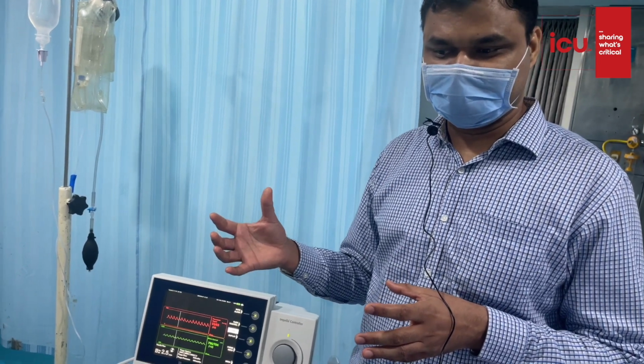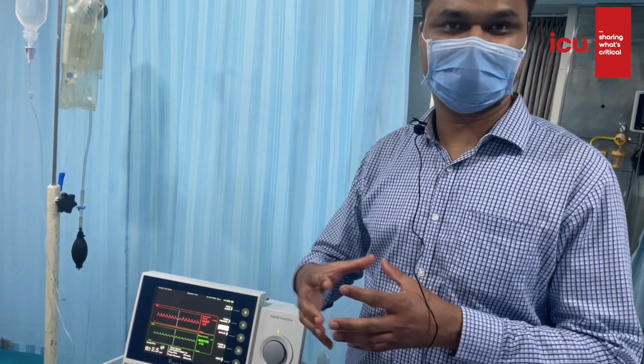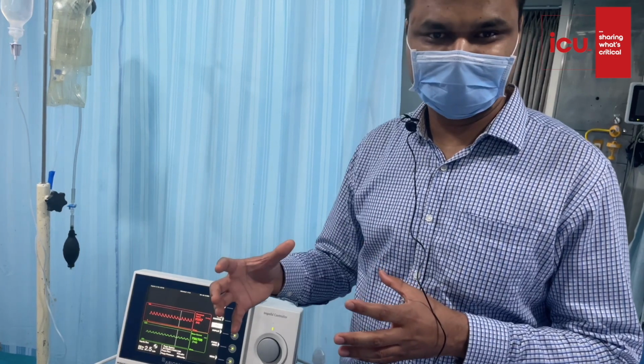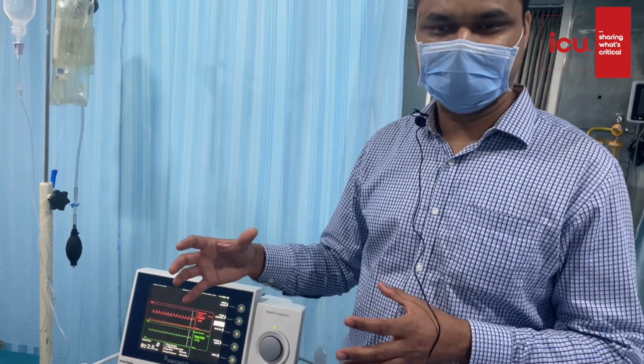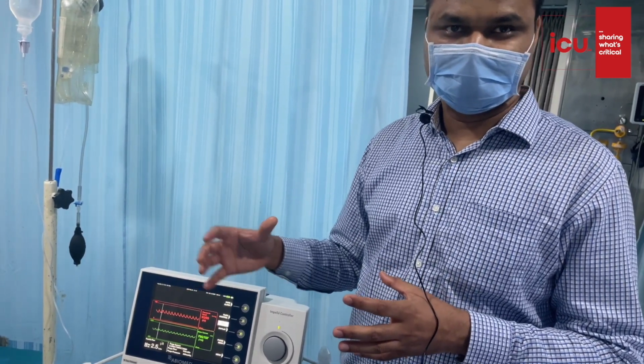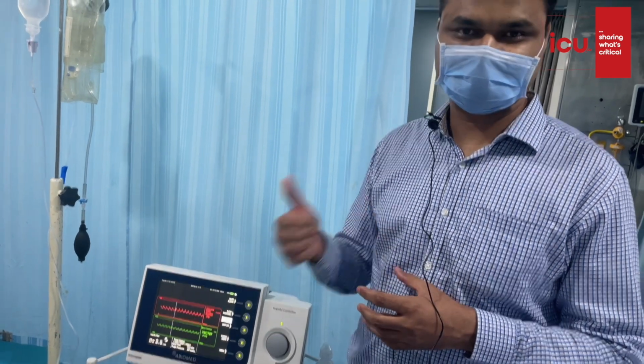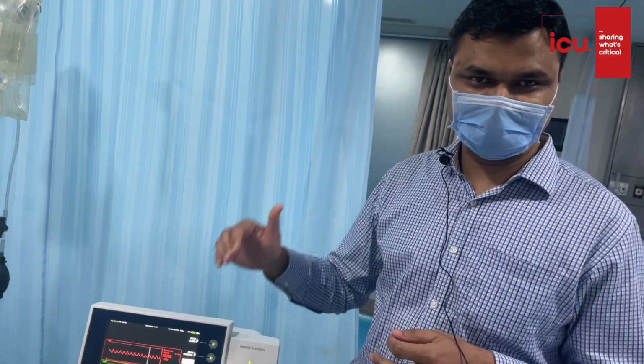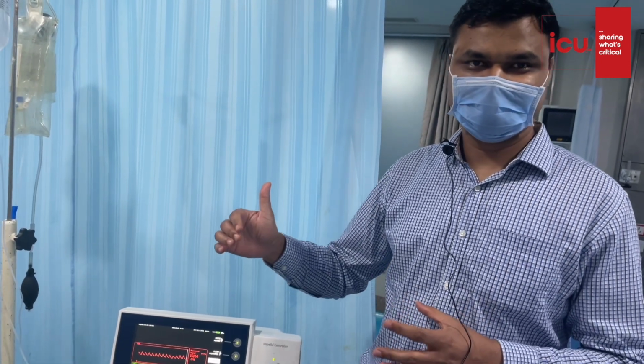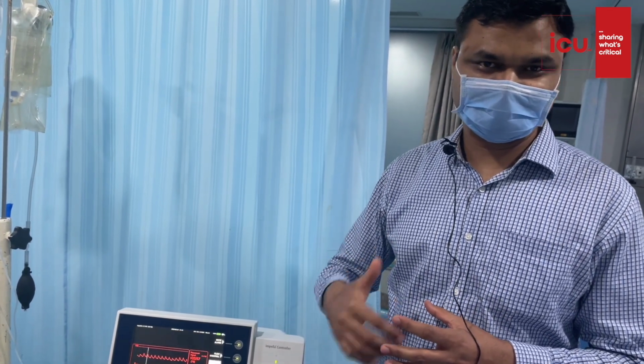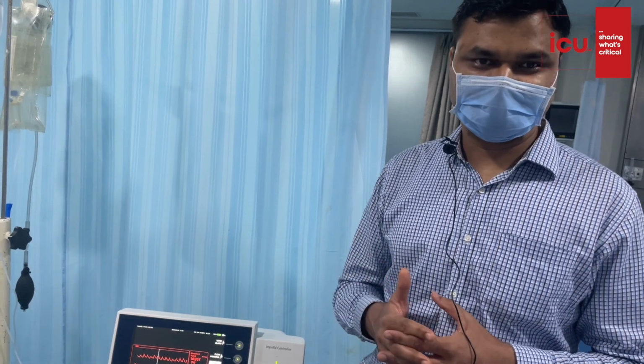Normal saline has a sodium ion which can crystallize the motor, and when the motor crystallizes, then the life of the motor also goes down. So we never recommend normal saline to be used in the purge system. Sometimes people ask us a question, what if the patient is diabetic? So if you look at the flow, the maximum flow is 30 ml per hour, which is not significantly high. And anyway, most of these patients who are in ICU are quite critical and they are on insulin protocol anyway. So that should not impact much on the patient management.